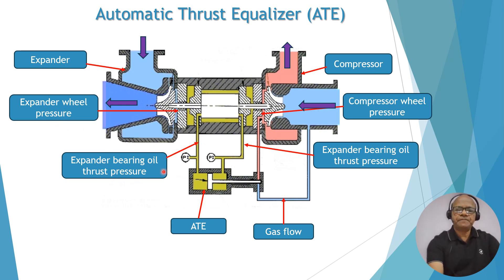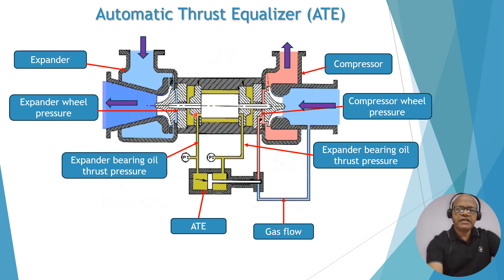The same arrangement is shown here. This is the expander inlet process gas, and the expander wheel pressure is visible here, along with the expander outlet. Similarly, this is the compressor suction and compressor discharge. This is the compressor wheel pressure and this is the expander wheel pressure. The bearing is fixed for both the expander and compressor sides while the rotor or shaft moves. When the shaft moves in one direction, the clearance decreases, and because of this the oil thrust pressure increases.